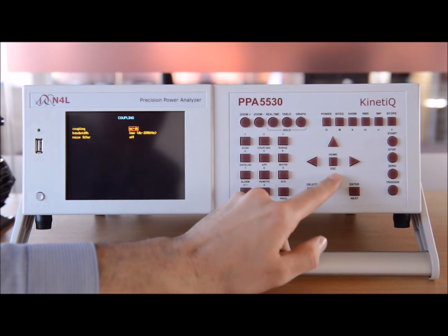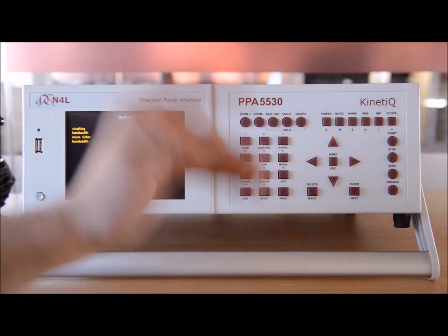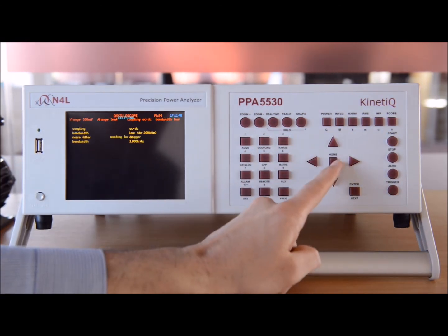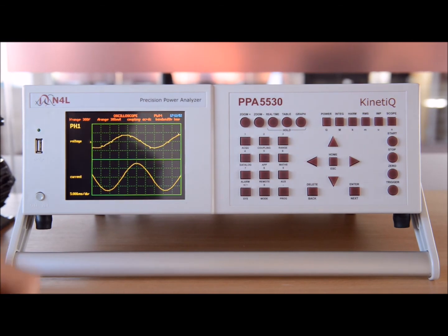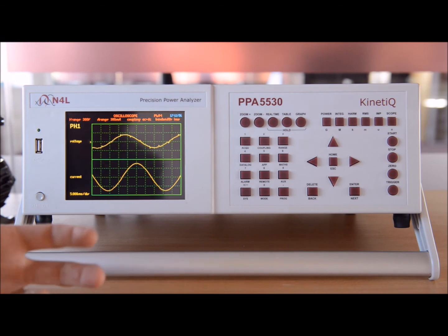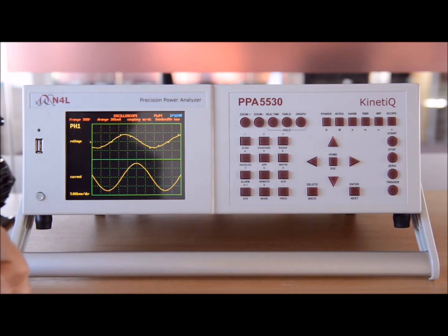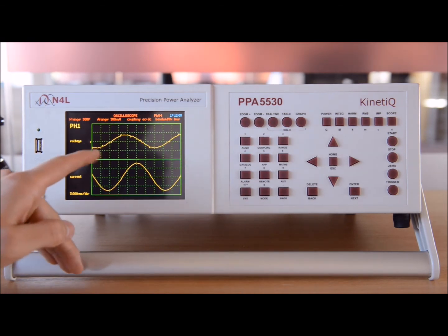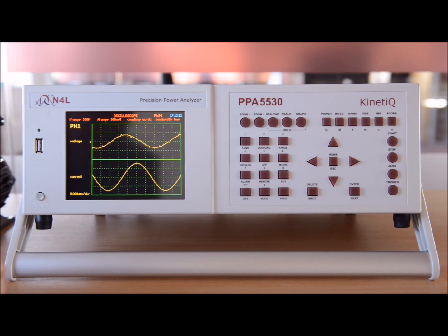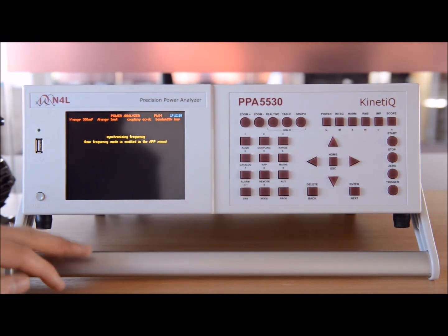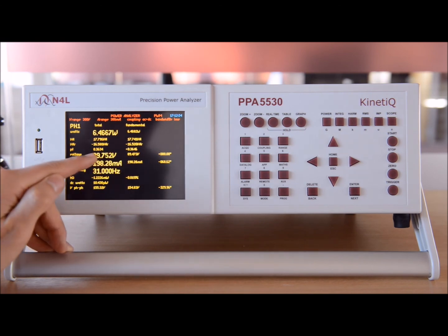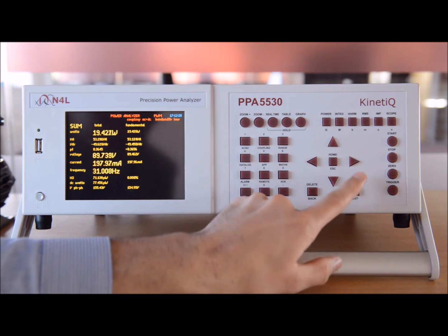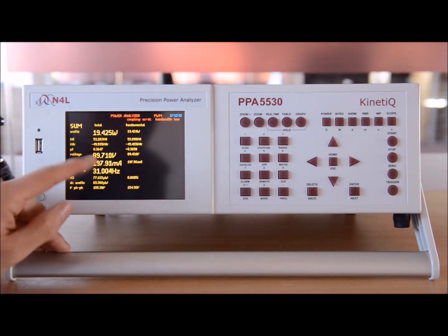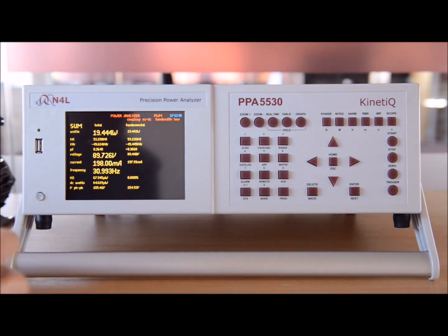Now I can apply an inline digital filter of, for example, 1 kilohertz, and this filter is in line. Now this is sometimes used in other applications where we genuinely aren't interested in the wideband power. I'm just using it here to demonstrate how some other analyzers on the market will have to filter the signal itself in order to lock on to this noisy fundamental frequency. Now let's see how that affects the numbers. As you can see here, that's brought the RMS voltage right down. Let's look at RMS power, 19.4 watts total power now, 89 volts now. So we're narrowing the bandwidth of the instrument.